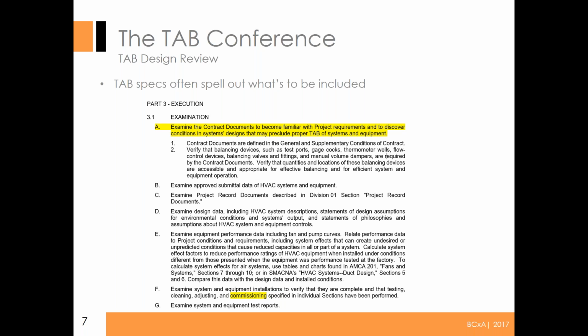So it says examine system and equipment installations to verify that they are complete and that testing, cleaning, adjusting, and commissioning specified in individual sections have been performed. So basically it's saying that you guys should have commissioned it before they do the test and balance, which is the exact opposite of what's normal and what's said elsewhere.